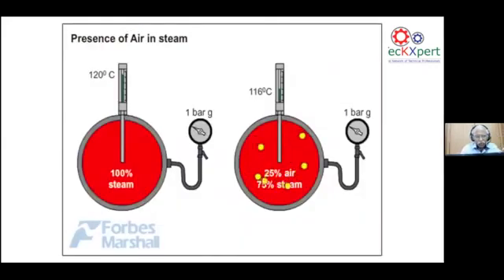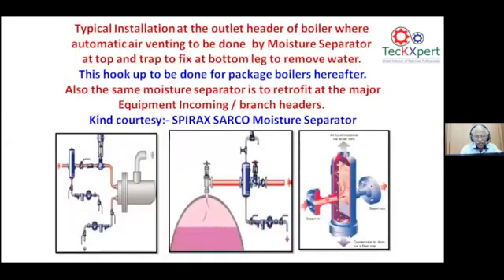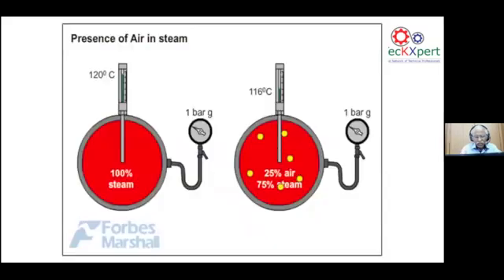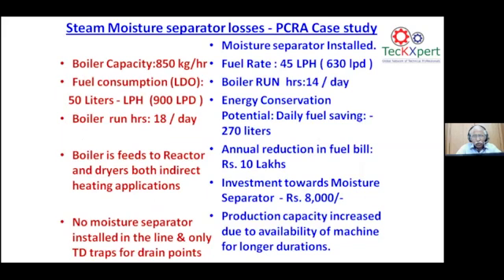You can see, thanks to Forbes Marshall, what 100% steam at 120 degrees looks like, and the air in steam. If the air is not removed from the steam delivery, and the air vent is not functioning at the moisture separator, this will happen: the temperature drops and the heat transfer efficiency of the steam also drops. So putting a moisture separator at the boiler end, definitely 10% savings is there.